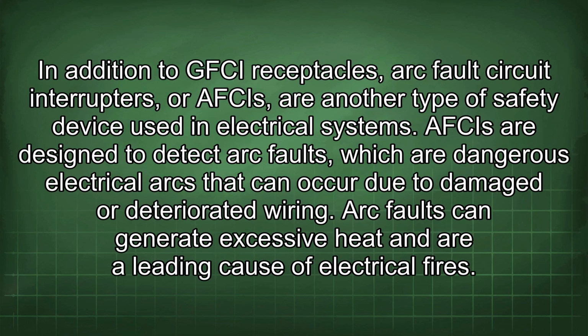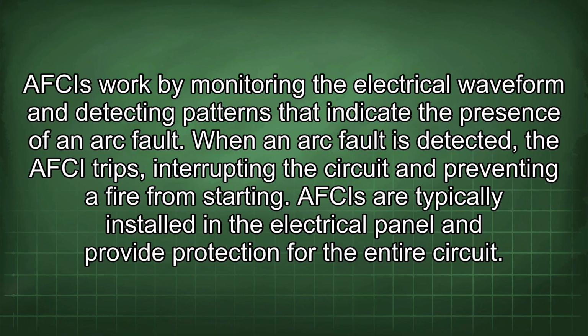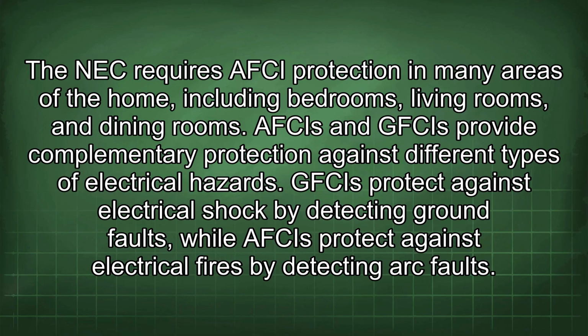compromised or ineffective. In addition to GFCI receptacles, arc fault circuit interrupters, or AFCIs, are another type of safety device used in electrical systems. AFCIs are designed to detect arc faults, which are dangerous electrical arcs that can occur due to damaged or deteriorated wiring. Arc faults can generate excessive heat and are a leading cause of electrical fires. AFCIs work by monitoring the electrical waveform and detecting patterns that indicate the presence of an arc fault. When an arc fault is detected, the AFCI trips, interrupting the circuit and preventing a fire from starting. AFCIs are typically installed in the electrical panel and provide protection for the entire circuit. The NEC requires AFCI protection in many areas of the home, including bedrooms, living rooms, and dining rooms.